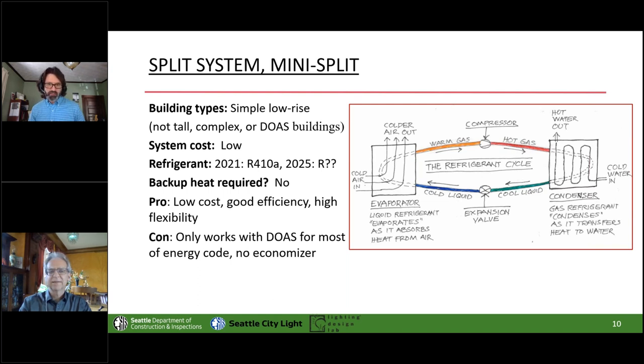But what really matters here is the compressor. You compress a thing, it makes it hot. If you've worked with air compressors, you've noticed this. The tank gets hot. And when you expand that pressure, that gas, it gets cold. So great. You compress it, it gets hot. You get rid of some of the heat. You expand it, and I might be admitting myself as a juvenile delinquent of yore, but if you've ever used spray paint long enough, you'll know that that can get real cold just from expansion. Same thing, gets cold, you absorb some heat again, you go back around, closed loop.